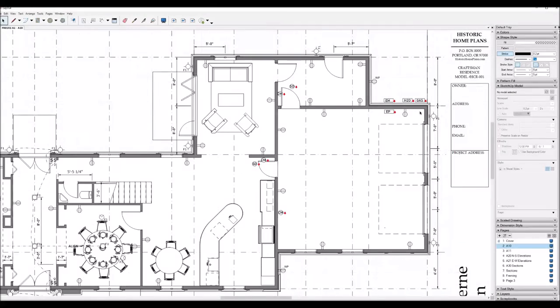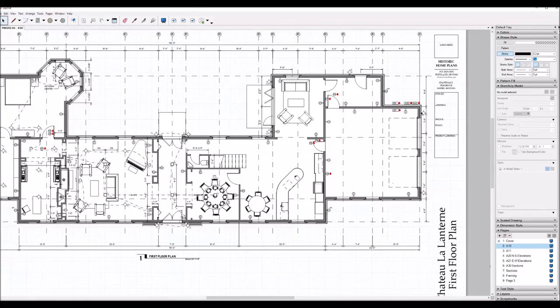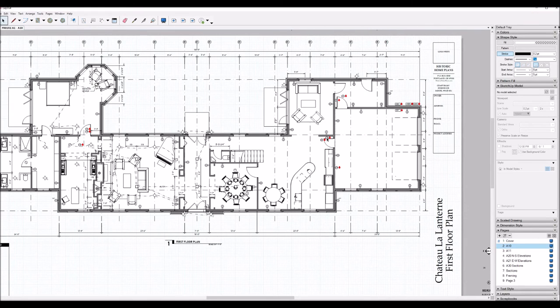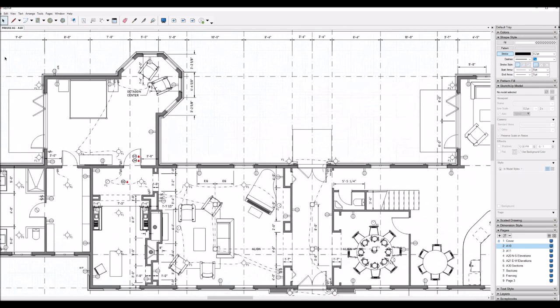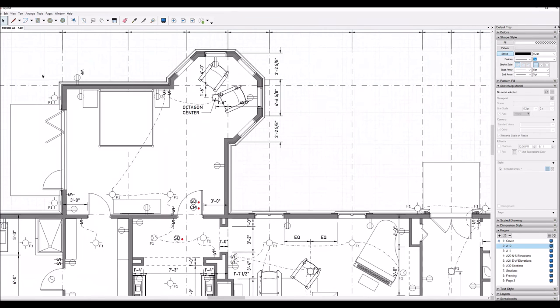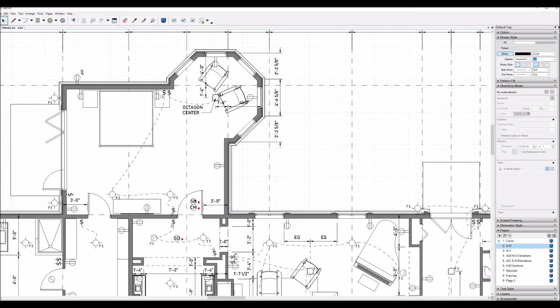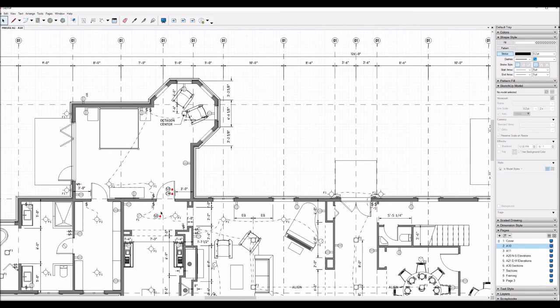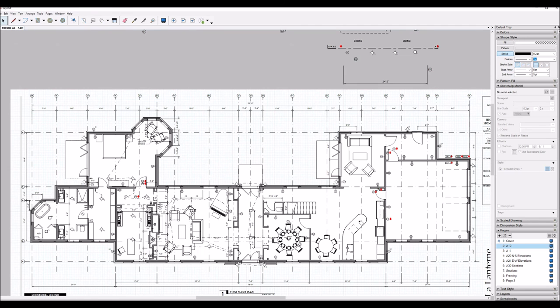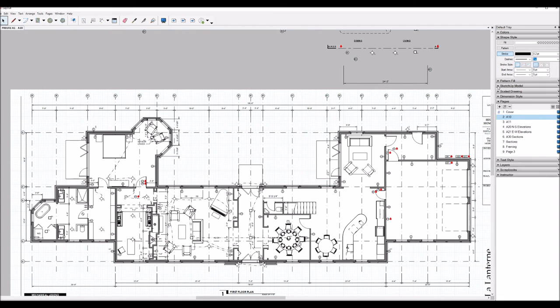Places where smoke detectors are required: definitely the garage doors between the garage and the house. Also in every bedroom, there should be one. I've placed it on the ceiling. You can get combined carbon monoxide and smoke detectors. So I'm recommending that for the bedroom and it's on the ceiling again, about two feet in from the door. If a bedroom is served by a hallway, the hallway should also contain a smoke detector. So I've got one in this little lobby space in front of the bedroom. I'm not sure that this one in this particular case could strictly be required by code, but given how cheap they are, I think it's advisable to do it anyway.